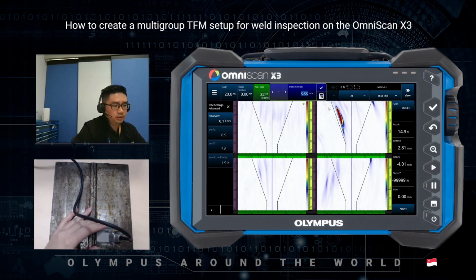Okay, so we get another signal over here. So this is on the full skip or 4T, and you can see that this signal gives you a very high amplitude on the sidewall, so it's a lack of sidewall fusion. We also see a little bit of it on the 5T, and even a little bit on the 3T over here.